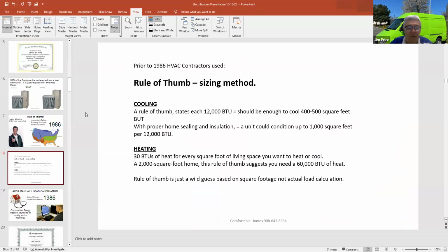This is the rule of thumb method, and everyone's going to get these slides, so I'll go through it fast. Essentially, they say 400 square feet of space requires 1 ton of cooling, and about 2,000 square feet in the home requires about 5 tons of heating. That's insanely oversized, especially for buildings done today, even the old stuff.